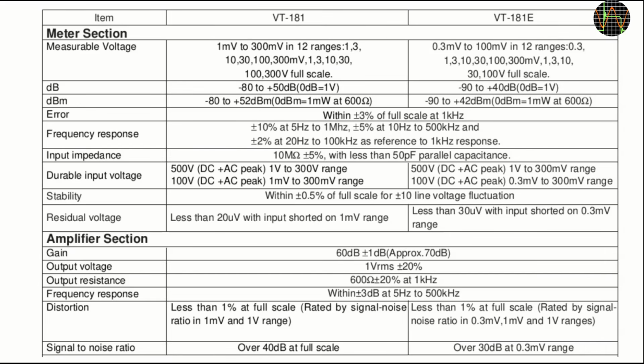The E version differs from mine in that it has a 0.3 mV range as the lowest range, where I have 1 mV. To make up for that extra range, the E model ends at 100 volts while I have an extra 300 volt range. In other words, the ranges on the E version are shifted by 10 decibels downwards. Everything else is the same between both models, except that the E version has slightly more residual noise. Both units have the same 60 dB amplifier.